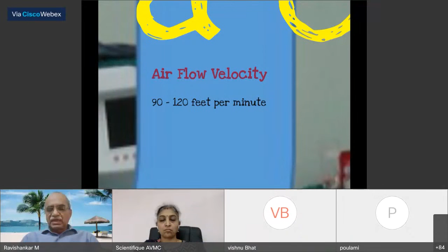And most important, the airflow velocity. The flow velocity should not be more than 90 to 120 feet per minute. Because if it is more than that, like if you put on a fan and sit inside, there will be a draught hitting you and flowing away from you. That kind of feeling should not be there when you are inside a laminar flow system. The flow velocity should be only about 1 foot to 2 feet per second. So you just feel that something is flowing, but it doesn't create any turbulence by hitting you. That is the recommended airflow velocity.